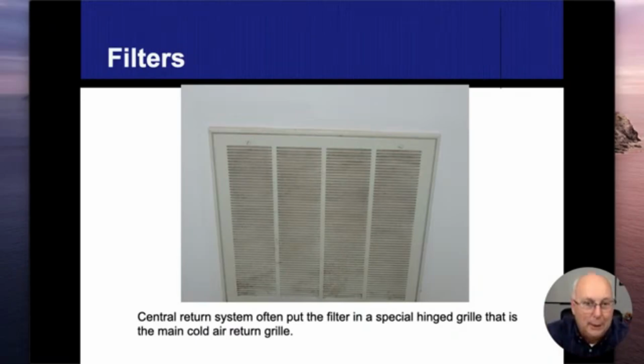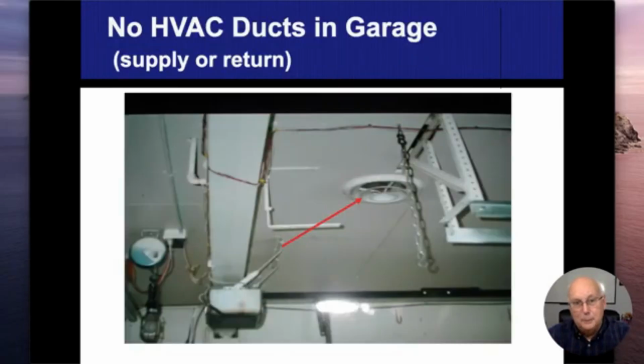And that actually shortens the lifespan of these furnaces, because those metals in that heat exchanger, everything, when it gets hot, it expands. When it gets cold, it shrinks. And they're only designed to work on a certain temperature rise. If I start overheating them or overcooling them, then that shortens their lifespan. We don't want to leave it like that. So making sure we're within that range is kind of a big deal to me.